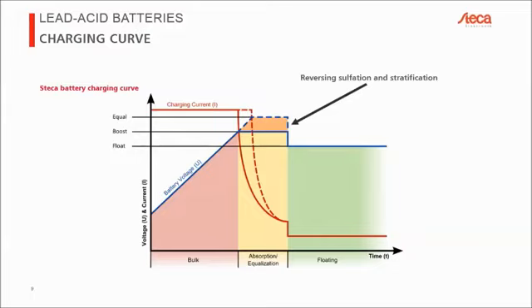So that's the desulfation. And then because this is almost like a carbonated drink, like a pop soda, it also has a mixing effect. So it will actually mix the electrolyte and therefore reduce stratification. Those are the two main effects for boost or equalization charge. And what equalization charge also does is this: in a 12-volt battery, you have 6 battery cells with 2 volts each. A controlled overcharging of the battery ensures that every cell has the same voltage. So that's what the term equalization means: we're equalizing the voltage of every cell in the battery.